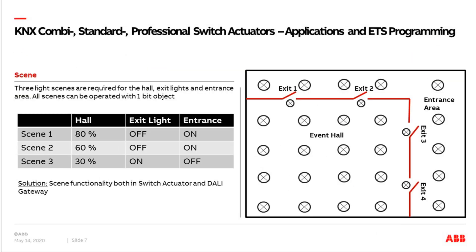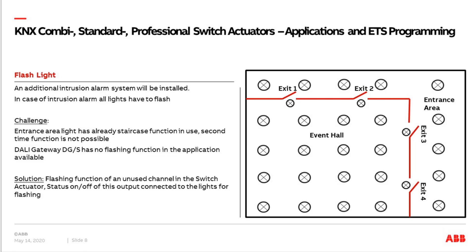Back to our project — this is an additional feature required. Last but not least, one more to show. Maybe later an intrusion alarm system will be installed. In case of any intrusion alarm, all lights shall flash — an additional alarm inside the building, switching on and off. We have the so-called flashing function in our switch actuators, available as a further time function. The challenge is that if you have already used the staircase function — as we use it in channel A for the entrance area — you cannot have a second flashing function anymore on the same channel. And the DALI gateway has no flashing function at all in the software.